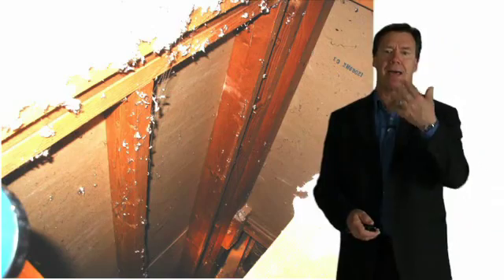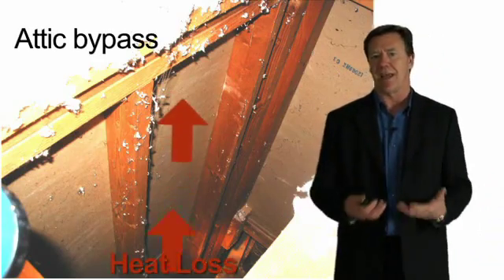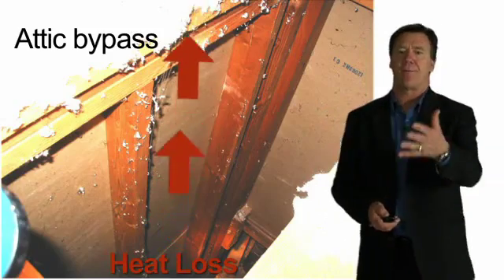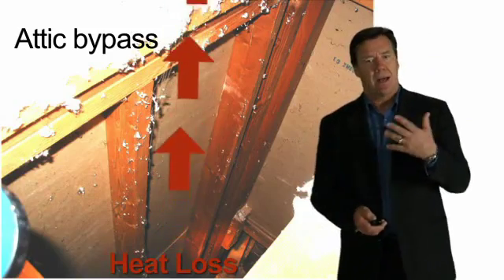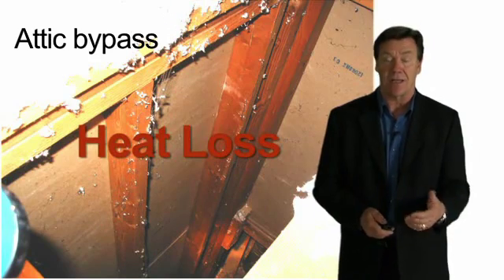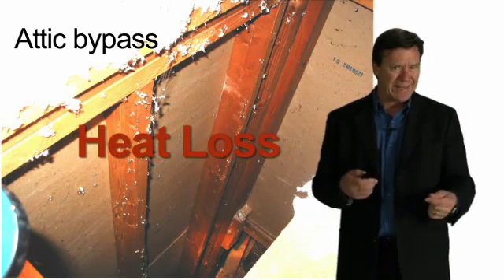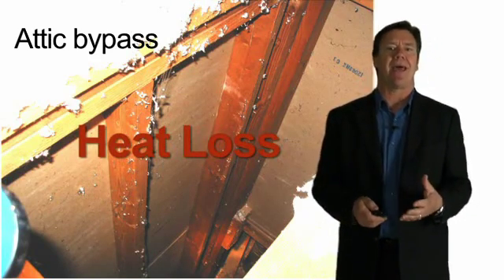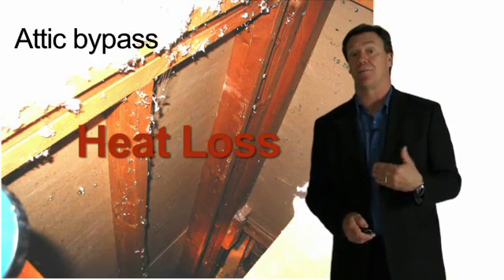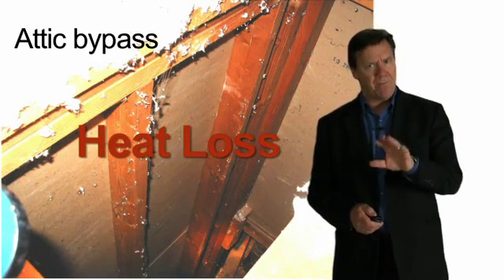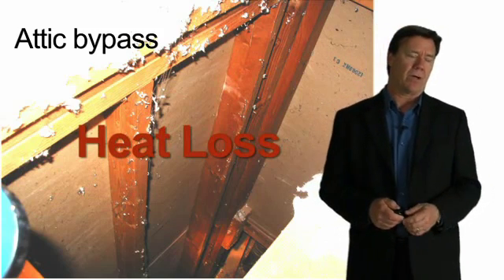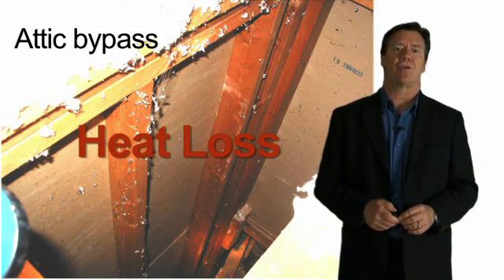We can't have big attic bypasses where air can easily exfiltrate up into the attic causing significant heat loss. This could be a drop ceiling or an HVAC chase. This is why we don't typically like building cavities used as return air duct, and the code does not allow building cavities to be supply air duct chases. These are areas to watch for with regards to air infiltration and exfiltration.